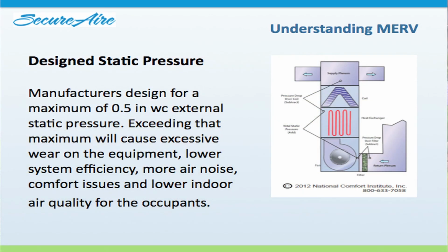As you know, when static increases, then everything negative that can happen with the HVAC system will. The system will get noisier, that's objectionable. The system's efficiency will reduce, that means utility bills are higher. We'll have a harder time getting proper airflow to the furthest parts of the house. That means comfort will go down. We don't do as good a job bringing particulates back to the filter. No matter how limited it might be, we're still doing it poorly.